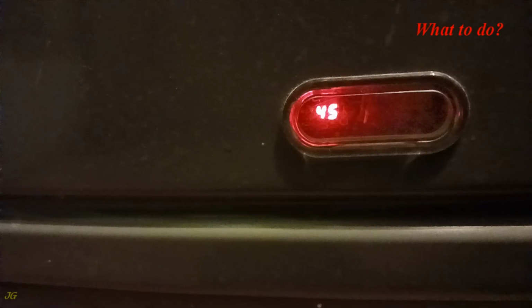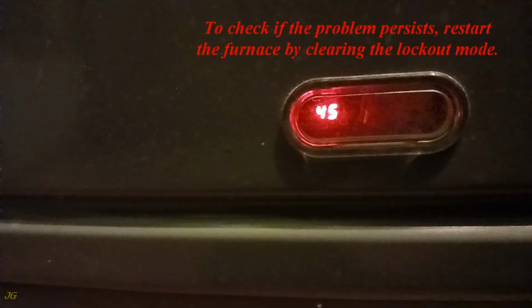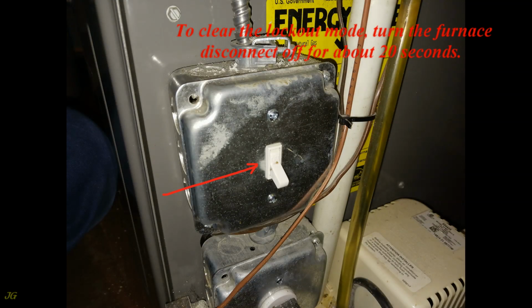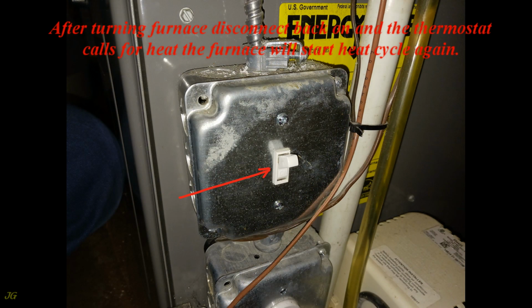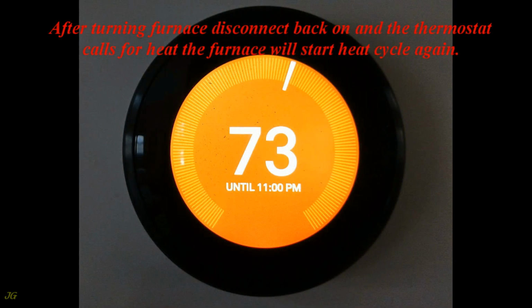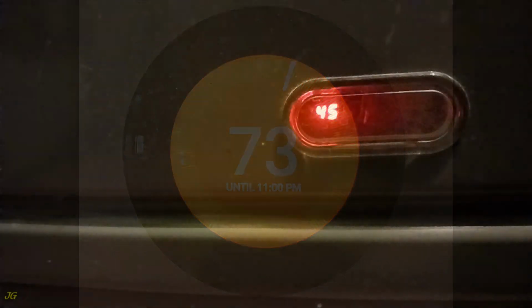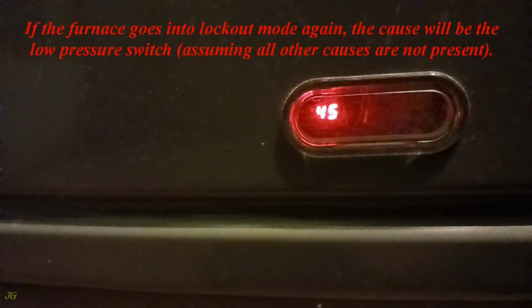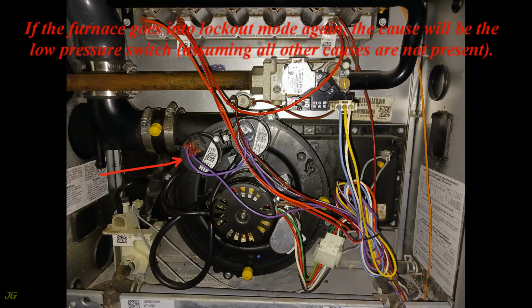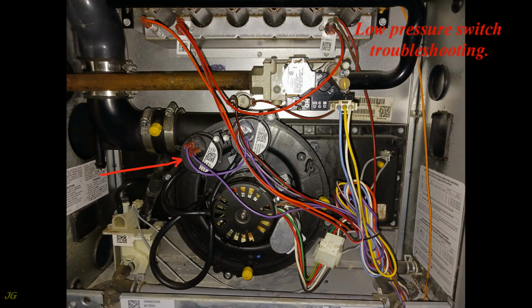What to do? To check if the problem persists, restart the furnace by clearing the lockout mode. To clear the lockout mode, turn the furnace disconnect off for about 20 seconds. After turning the furnace disconnect back on and the thermostat calls for heat, the furnace will start the heat cycle again. If the furnace goes into lockout mode again, the cause will be the low pressure switch, assuming all other causes are not present. Low pressure switch troubleshooting.